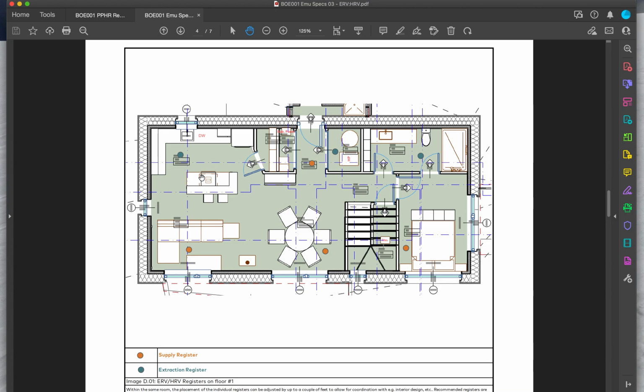A medium, traditional kitchen exhaust is about 400. So even in boost mode, the register from the ERV system extracts only about 8 times less than you need to get rid of the fumes from cooking. So as we covered in the other document, you want to have the traditional exhaust with a motorized damper, and there's indication of that in this document here.